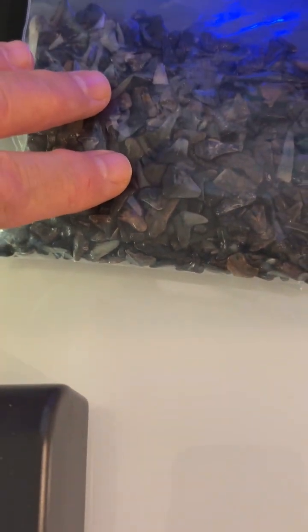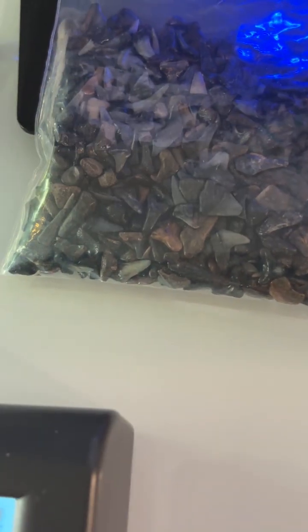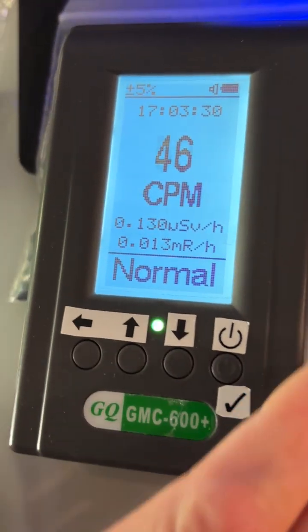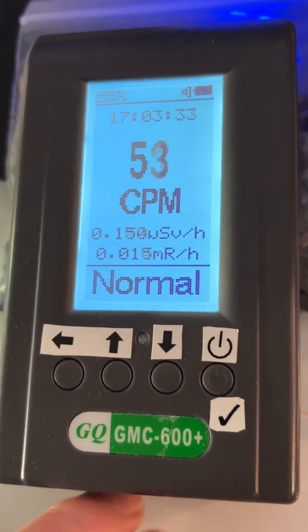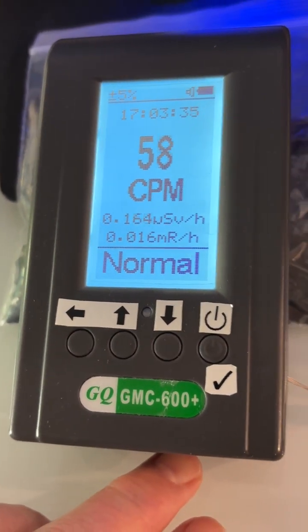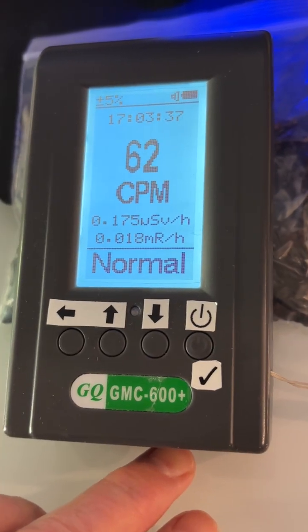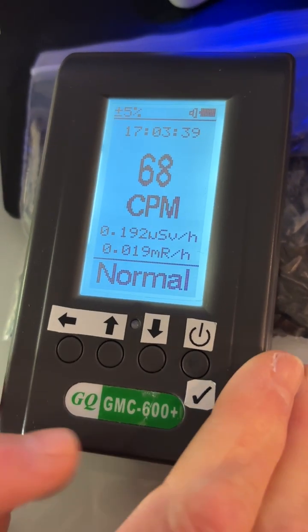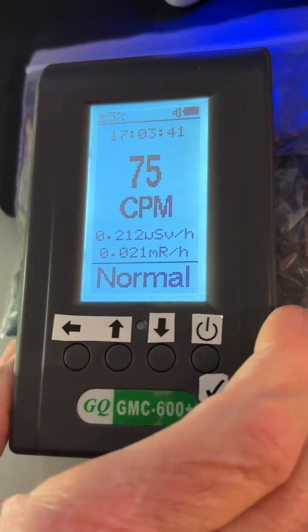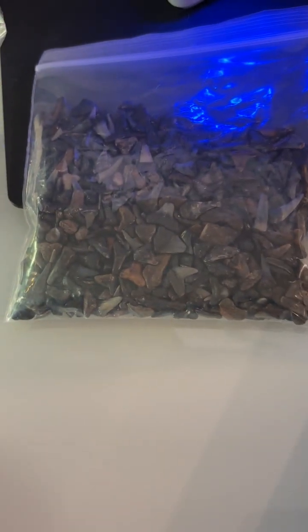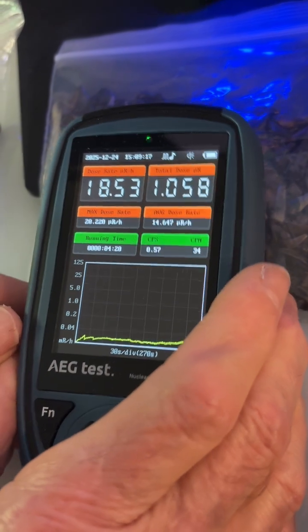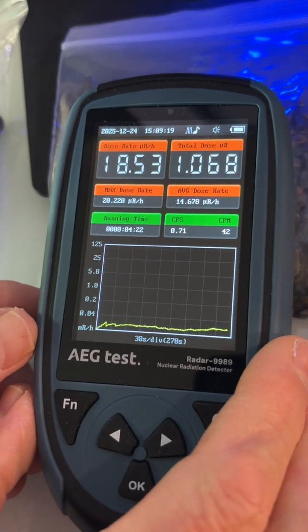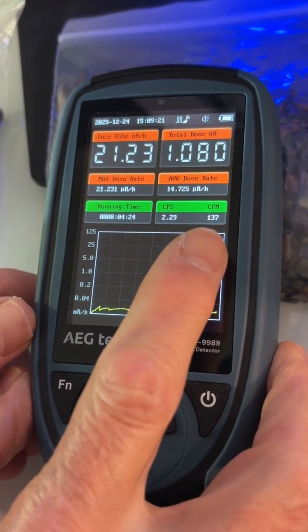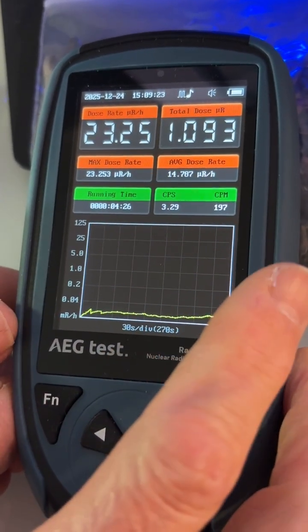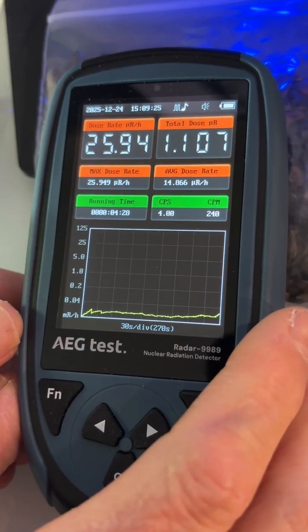These are some fossilized shark's teeth that were collected from a beach here on the west coast of Florida. We'll just put the GMC unit on there. And you can see it does start clicking up, but rather slowly. And again, it's set to 60 seconds too. But it does go up, it will respond. The AEG, on the other hand, is way more sensitive. There's your number. It's already up to 171, where the GMC didn't even get a chance to break 100.